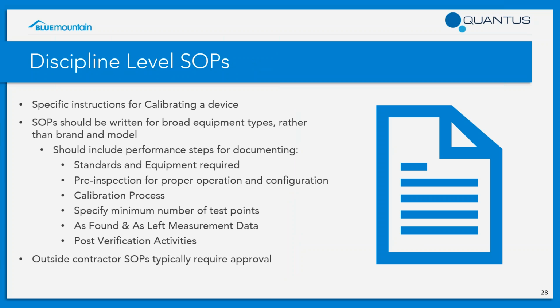All right, discipline level SOPs. I'm going to take a moment here to talk about this a little before we get into history files. If you have an internal calibration division, you're also typically going to want to have discipline-based calibration SOPs. We call them discipline-based because we really recommend writing them around the service function of the equipment. So this would be general pressure, general temperature calibrations, and you're going to want to avoid writing calibration procedures that are device specific to a particular incubator model or centrifuge model.